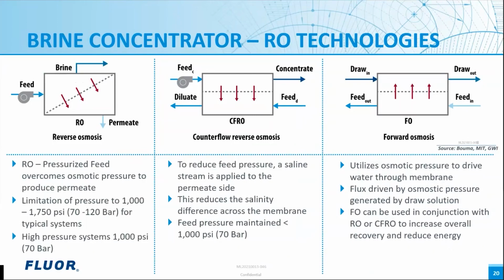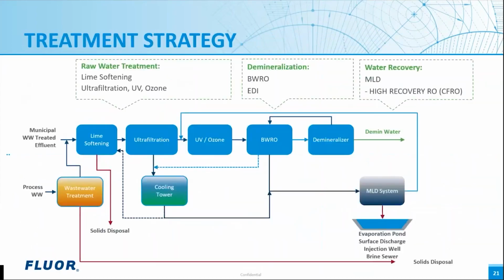This essentially means that high salinity feeds can be treated at a hydraulic pressure which never exceeds 1000 psi, approximately 70 bar, which enables the use of commercially available equipment. To attain higher recovery, brine is cascaded through multiple stages. Each type of reverse osmosis system shown above can be used in conjunction with one another in order to increase the overall system recovery.